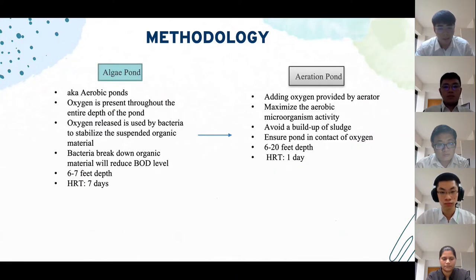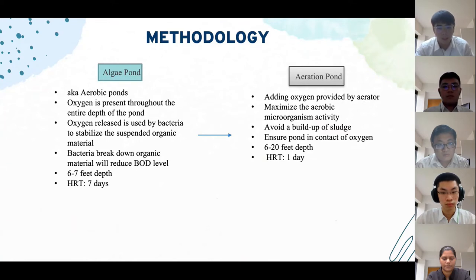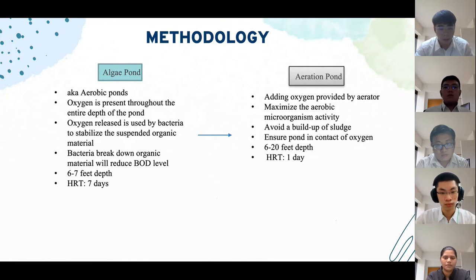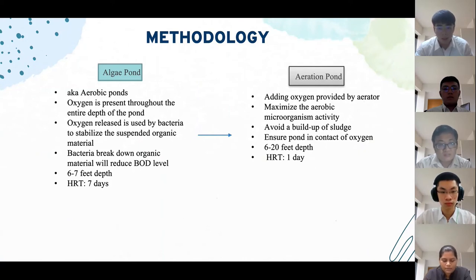Proceeding to the algae pond, also known as the aerobic pond: these are ponds where oxygen is present throughout the entire depth at all times to promote photosynthesis of algae and microorganisms. The oxygen released from photosynthesis is used by bacteria to stabilise the suspended organic material in the wastewater. Bacteria use the oxygen to break down organic matter into simpler compounds, reducing the BOD level. The algae pond is usually 6 to 7 feet deep with an HRT of 7 days.